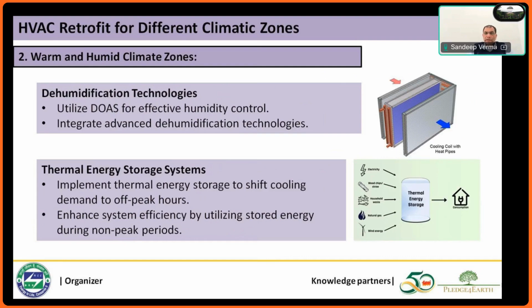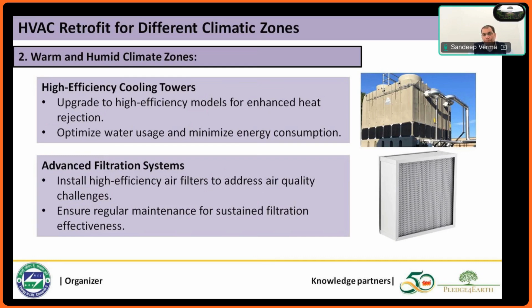In a warm and highly humid climate zone, since evaporation is very limited, you either have to go for bigger cooling towers in order to achieve the desired evaporation to ensure proper cooling, or it is recommended that you go for a high efficiency cooling tower. High efficiency cooling towers are available with multiple features, like the kind of filling material, the kind of nozzle, and fan speed control technologies. So we have high efficiency cooling towers, and they are very much recommended in a warm and humid climate zone.